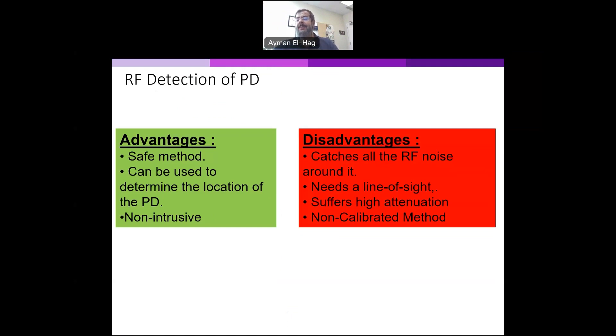Finally, it is a non-calibrated method. Because the emission that you are receiving does not reflect actually the actual value of the partial discharge. It reflects that there is a partial discharge, but it does not actually reflect what is the value of that partial discharge, because of the attenuation, because of the distance, because of the medium between the source and the antenna, and because of many other reasons. It is not possible to calibrate the magnitude of that partial discharge.